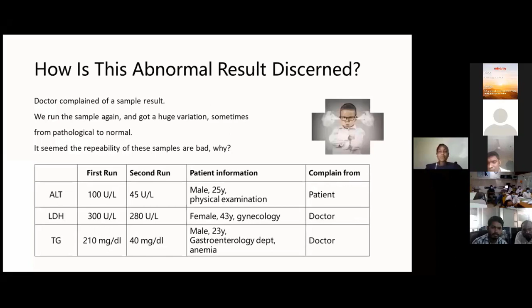Now, we decided to do a deep review of this phenomenon, and we found that the abnormal results had some common features. You'd find that the second run is normally good. Only the first run with mixed tests was affected. Sometimes the LDH would be very high if the test was followed by an LFT. Another feature was that the reaction response was higher in abnormal first runs. Also, in almost all cases, the second run results were lower than the first run. For example, the first run ALT was 100, second run 45.